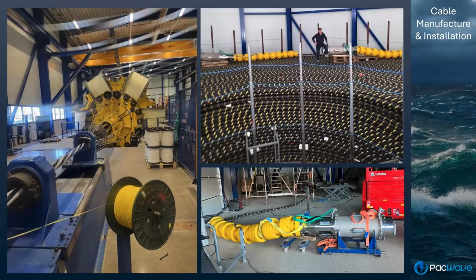So he's standing between two of our connectors that go on the ends. You also have a close-up of one of them. So you actually have the connector piece itself, or half a connector to be exact, because the developers will bring the other half. And then these yellow bend restrictors are critical for handling that cable in all the installation, so as not to overbend it. It'll damage both the fiber optics and the conductors, and this cable is incredibly expensive. You'll see for all the installation, one of the key things was maintaining that minimum bend radius. Combine these two, the connector and the bend restrictors weigh about a ton, and you'll see the relevance of that in a minute.